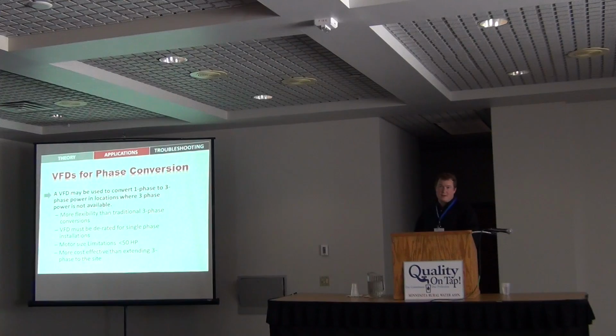The VFD must be derated for single phase installation, since a 7.5 horse VFD is rated for 7.5 horse three-phase. Now, if we're running single phase input into that VFD, it needs to be derated. So be aware, if you're doing a situation like this, suppliers should have charts showing the derating. I think a lot of times it's about 50% derated, so you'd be putting in a 15 horse VFD for a 7.5 horse motor. There are size limitations, about 50 horses is as big as you can go.